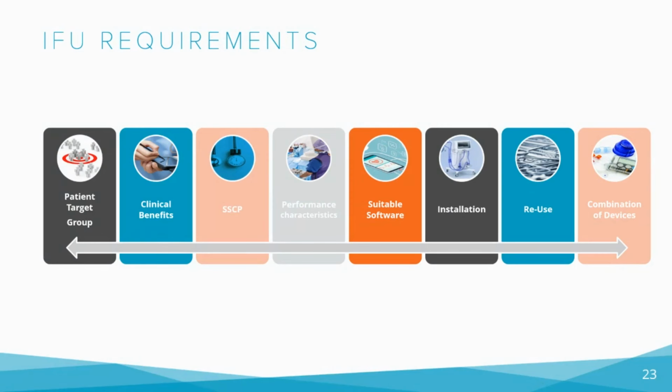This ensures that users can understand the information provided in the IFU in their own language so they can use the device safely and effectively. In addition to these requirements, the EU MDR also requires clinical benefits and performance characteristics in the IFU if applicable.